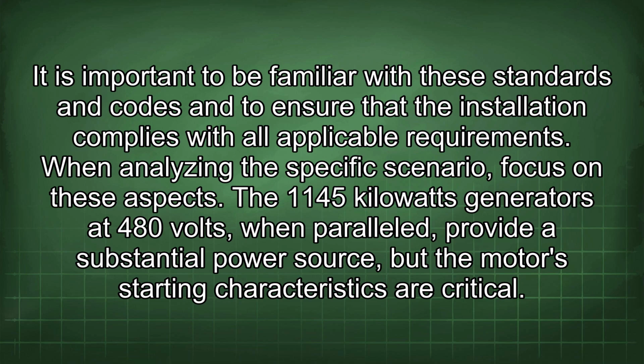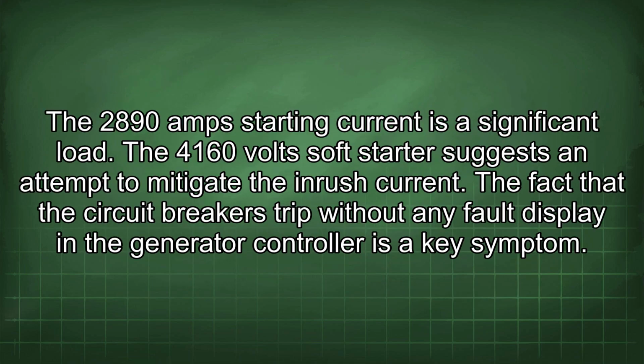1145 kilowatt generators at 480 volts, when paralleled, provide a substantial power source, but the motor's starting characteristics are critical. The 2890 amp starting current is a significant load. The 4160 volt soft starter suggests an attempt to mitigate the inrush current.